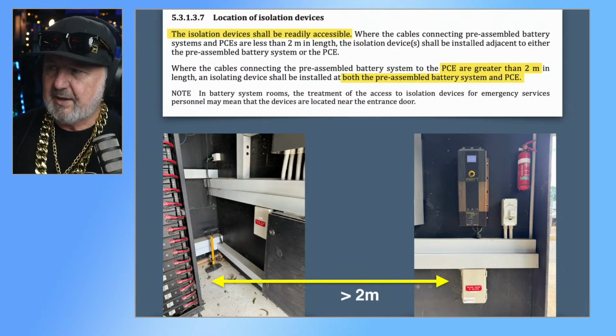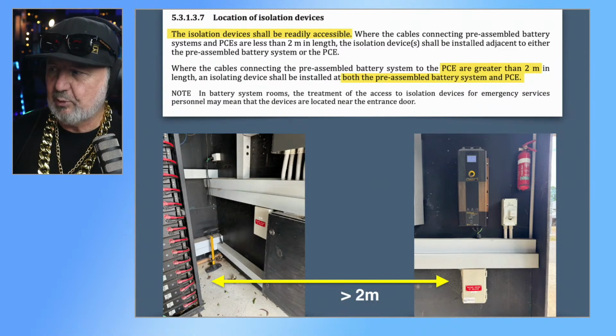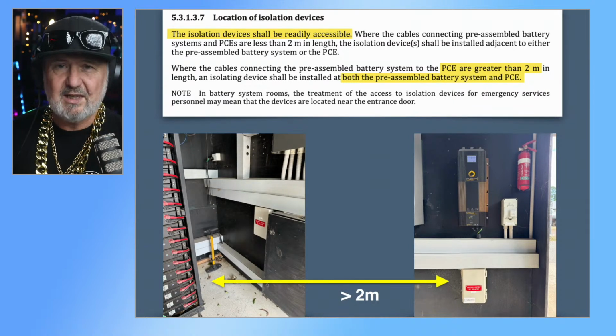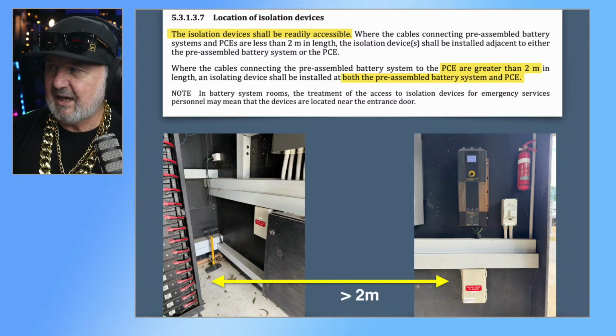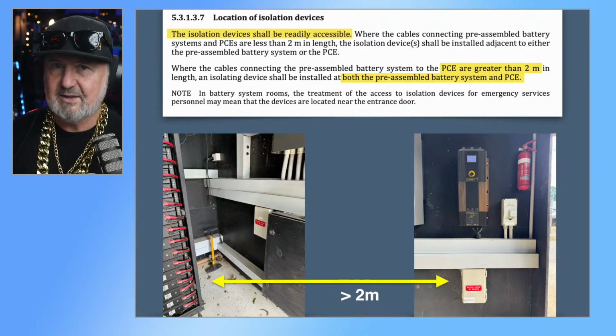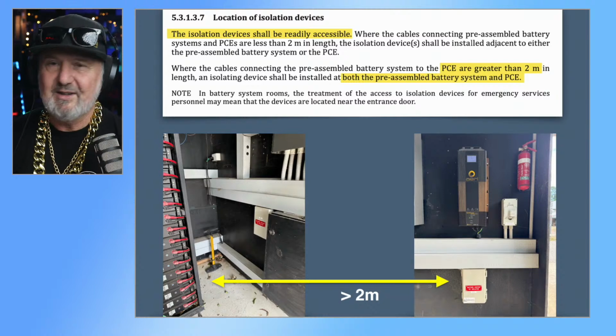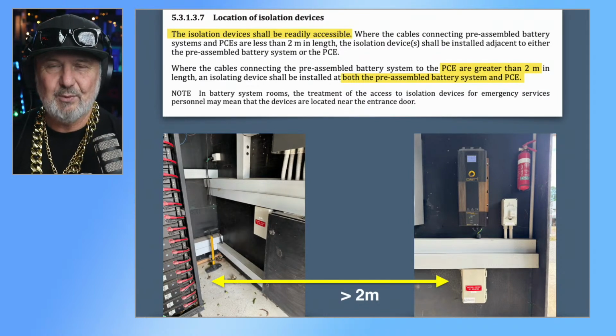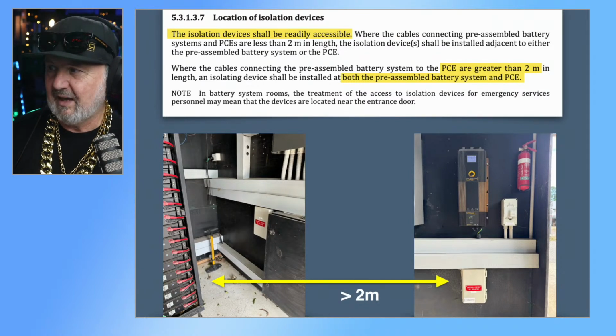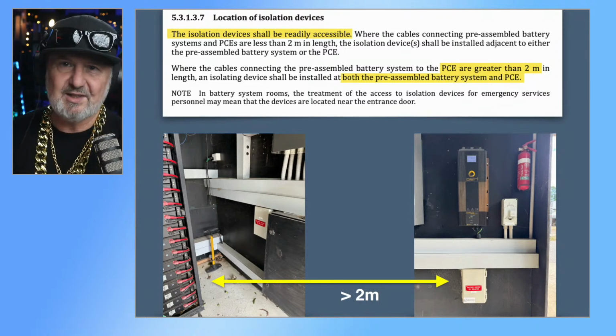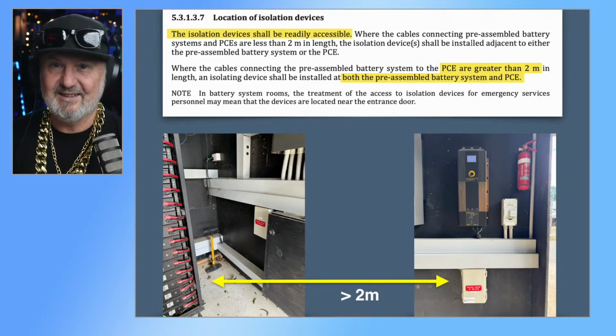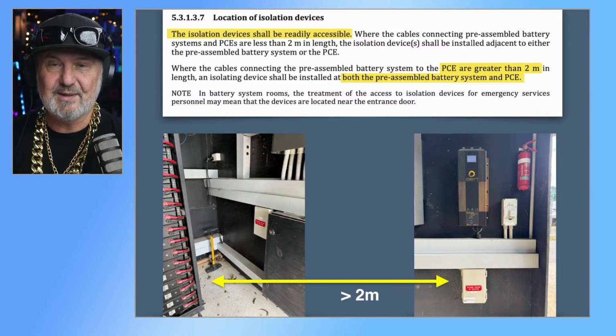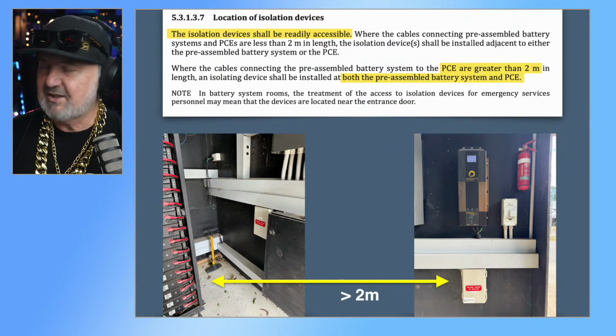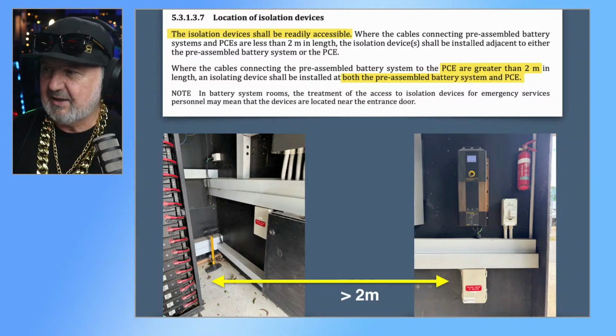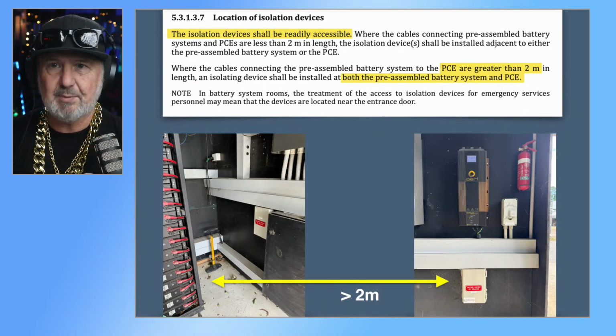It goes on in the second paragraph where the cables connecting the pre-assembled battery system to the PCE, so from the battery system to the PCE, are greater than 2 meters. So this is the 2 meter rule. In fact, the wording changes in the standard. One place it says 2 meters of cable length, and somewhere else it says 2 meters of distance. There you go. There's already a problem. They haven't been consistent with the wording, but let's just go with 2 meters of cable in length. An isolating device shall be installed at both the pre-assembled battery system and the PCE.